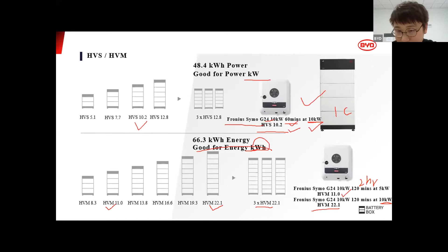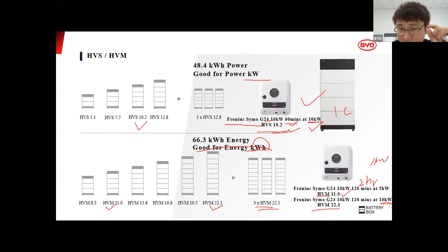But if you're considering emergency backup, for example, there's a blackout and the customer doesn't want to just turn on the lights or the TV. They want to turn everything on. Then this will be your choice, because it is able to deliver that 10 kilowatt for the backup, but only for 1 hour. But sometimes it's, okay, when the grid is down, I need to minimize my power and I just don't need that much. Then I just need a larger size of batteries to give me autonomy of the system, lasting a few days, just running 1 kilowatt. Then the HVM is definitely your choice. And with the same size of battery, the HVM is a little bit cheaper.